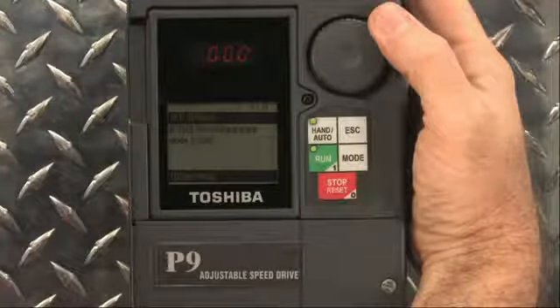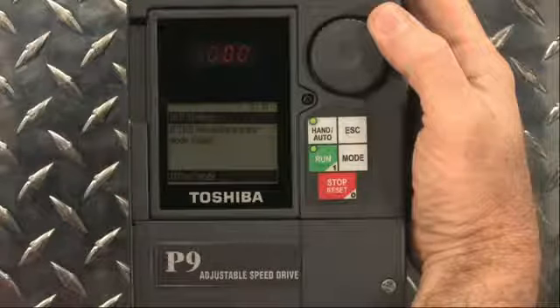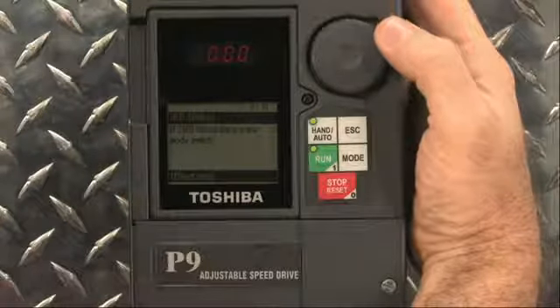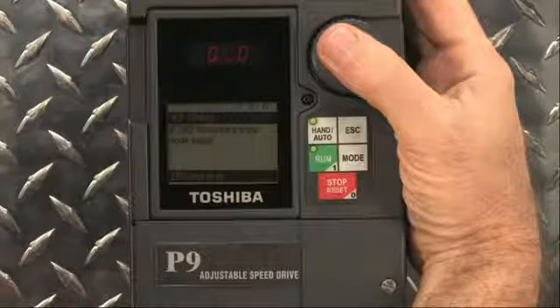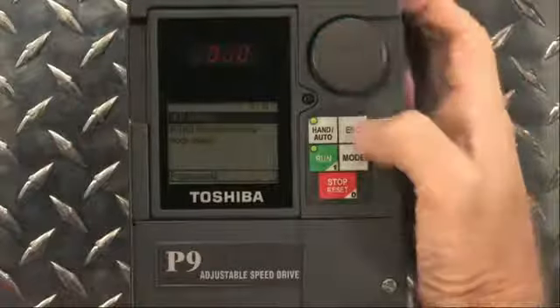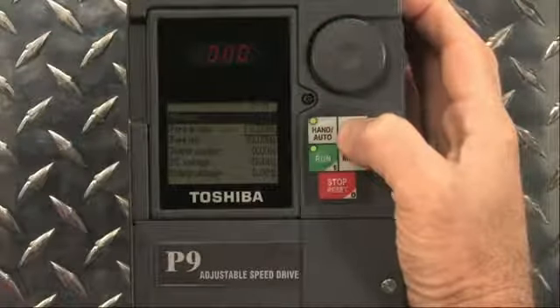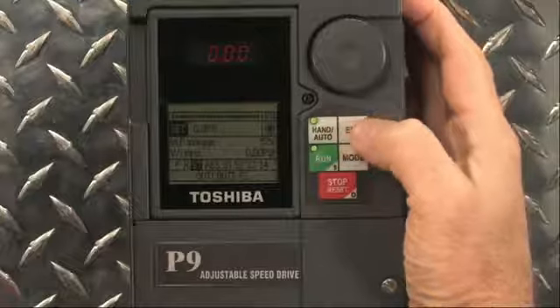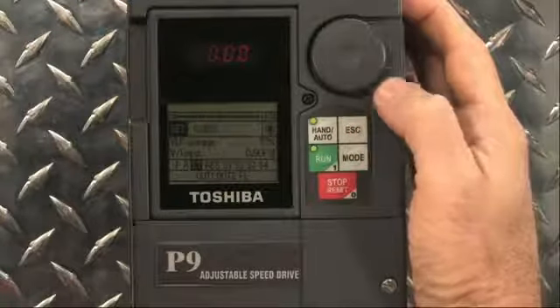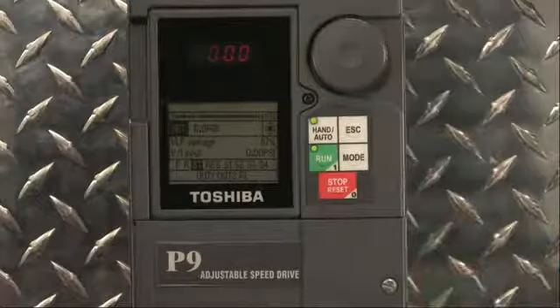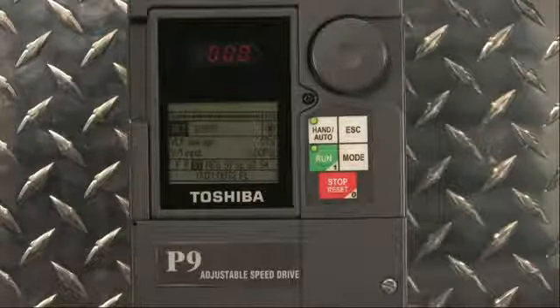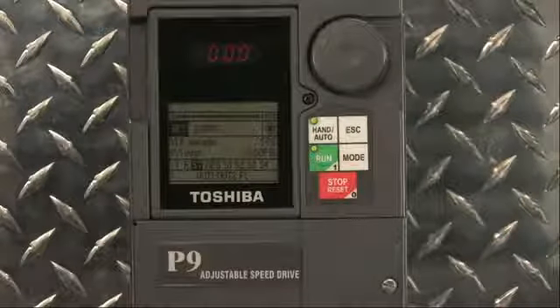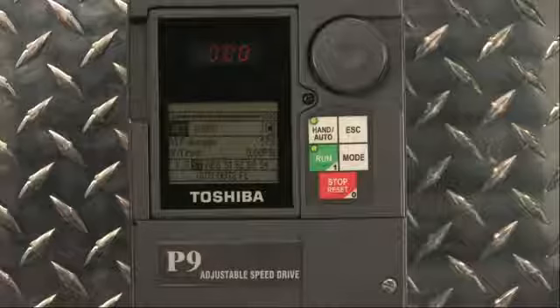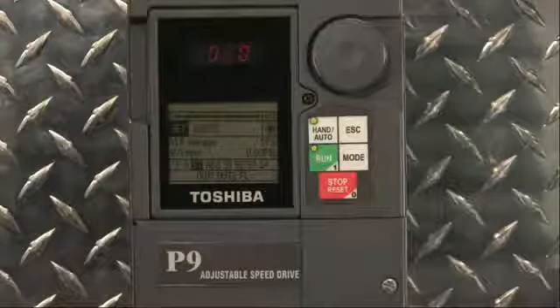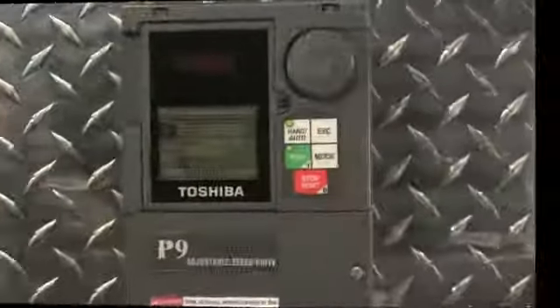To enable VLP, select this parameter, scroll to Process Hold, and then press Enter. The other option, Direct Mode, should be used when operating without transducer feedback. Since this system uses a transducer, we select Process Hold. After this, press Escape until we are back to the main operating screen. Notice our set value is displaying in PSI and the current value is 0.0. Also notice the two monitored items. The first monitored item will be the analog input that the transducer is connected to. It will also display in PSI, which allows for direct comparison between set point pressure and feedback pressure. The second monitored item is the current VLP number the pump is running at.